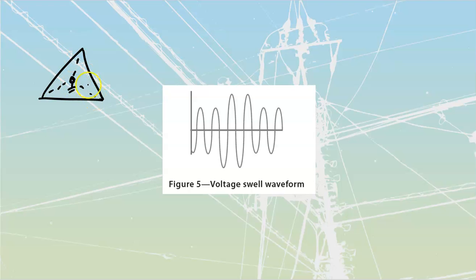All the voltages balance around that center point, because nature tends to want to balance. But as soon as I ground one corner of the system, that moves the ground over. Now we're physically attached there, not necessarily on purpose, but because a line made contact, or there was an accident. As a result, say this was a 600 volt delta, now this point is sitting at 600 volts above ground, and the other one is sitting at 600 volts above ground too, whereas before they were all just hovering at 347 volts above ground. We see it's a massive amount of voltage.